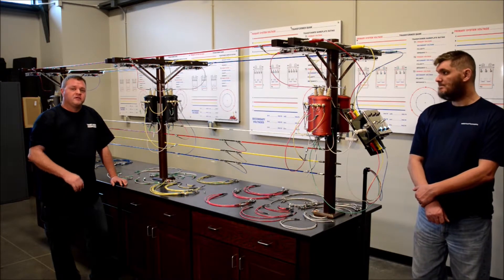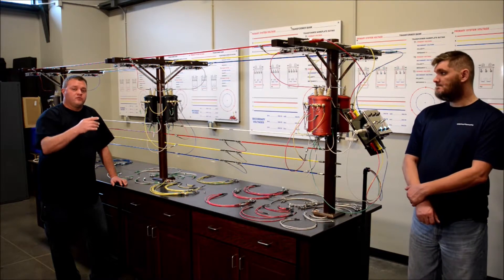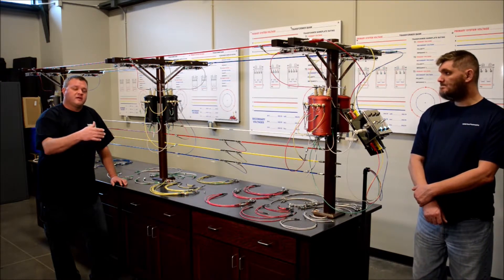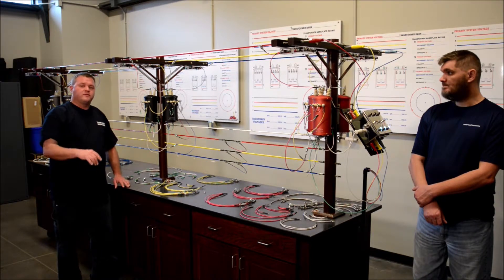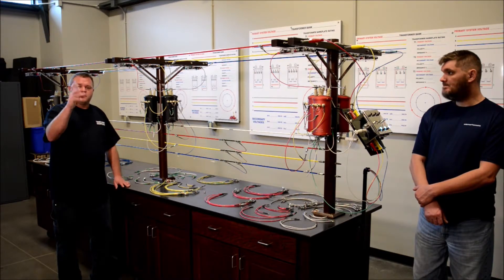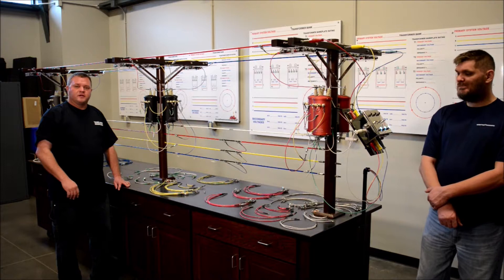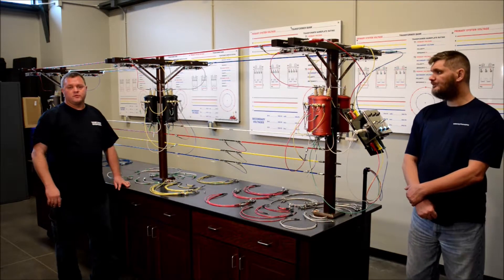This is the harmful effects of backfeed as far as going to do repair on the line. Say I've got two lines down. Hey, the cut outs are open. Those two phases are dead. Let's just pick them up and send them up to the line. He's ready to go. This is why we don't do that.